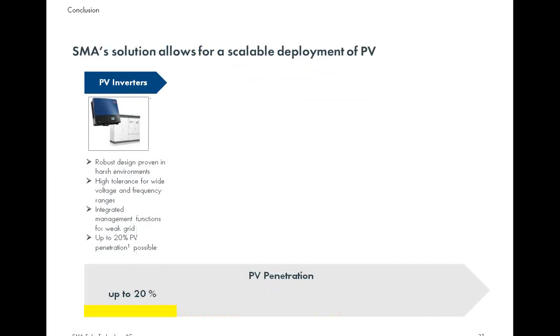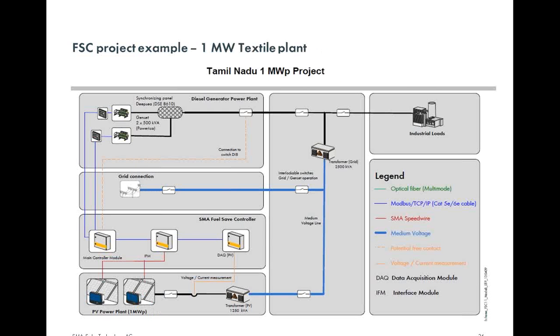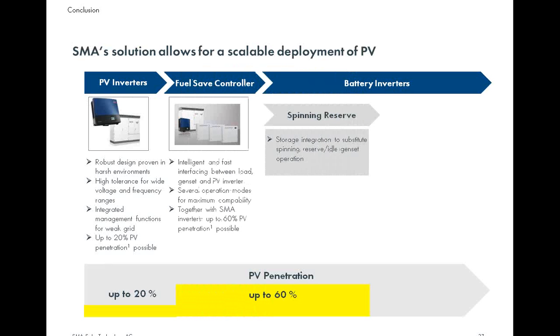And in this we also have a provision to feed the extra power to the grid. During the day, for example, if the PV is extra, which is not needed by the load, we can also feed that into the grid because there's a bidirectional meter available here. All right, just to recap, if you want up to 60% penetration of solar, you obviously need the Fuel Save Controller.